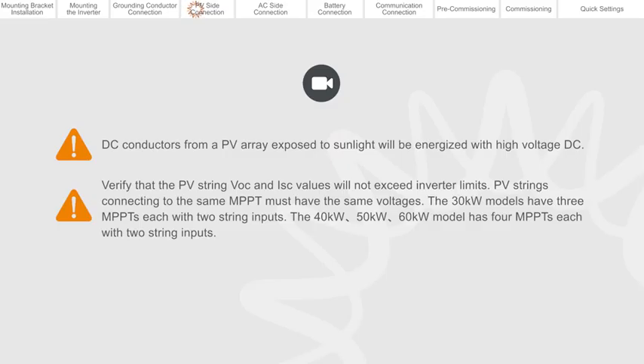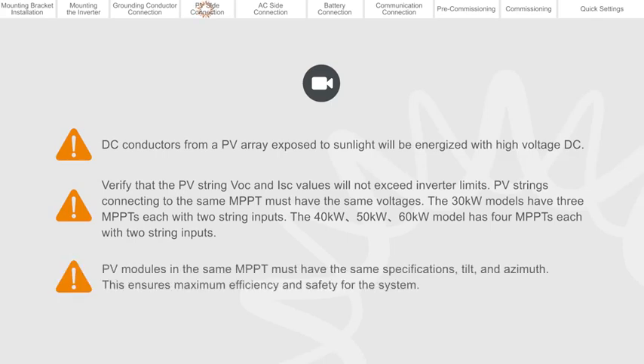The 30 kilowatt models have 3 MPPTs each with 2 string inputs. The 40 kilowatt, 50 kilowatt, and 60 kilowatt models have 4 MPPTs each with 2 string inputs. PV modules in the same MPPT must have the same specifications, tilt, and azimuth. This ensures maximum efficiency and safety for the system.